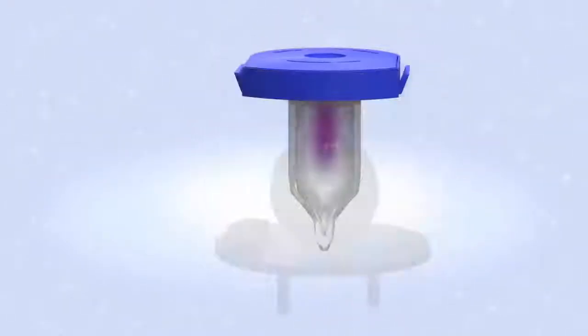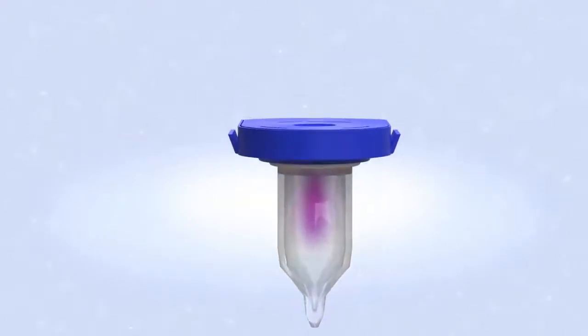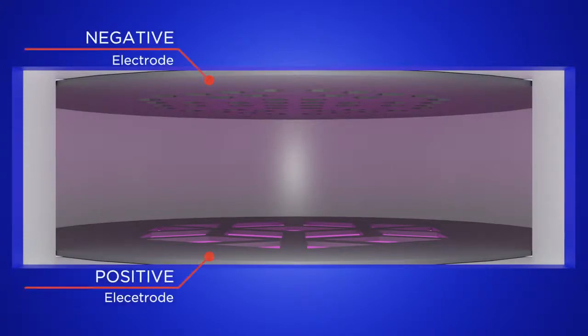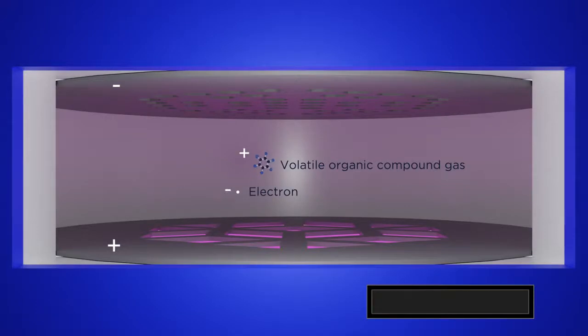Typical photoionization sensors consist of a high-energy ultraviolet lamp and two electrodes. Volatile organic compound gases enter the detection chamber and are ionized by the ultraviolet light. A negatively charged electron is ejected from the molecule, making it positively charged.